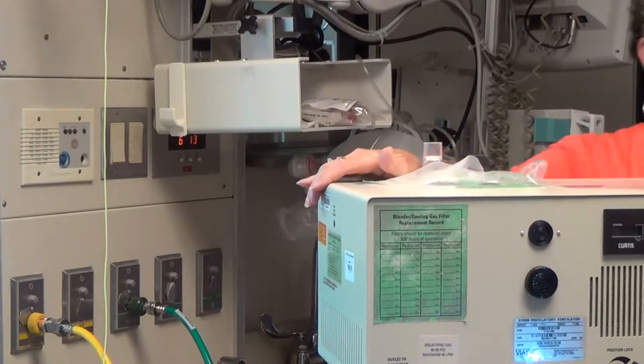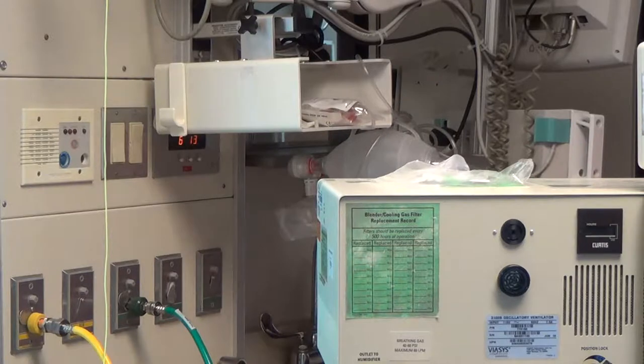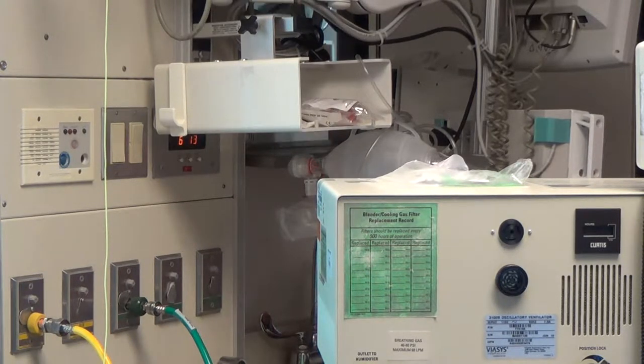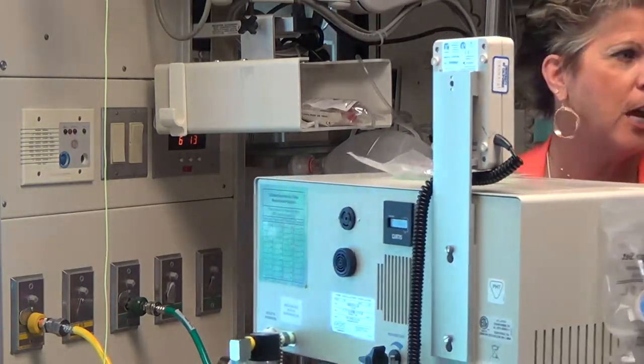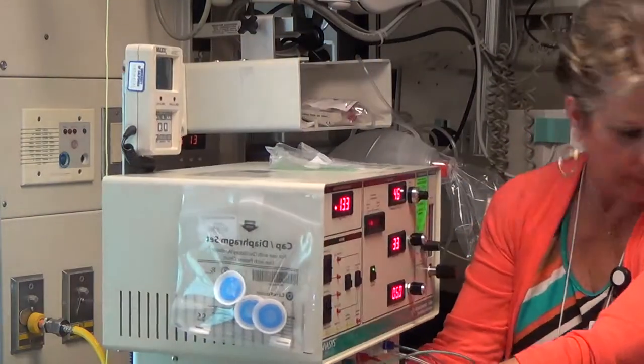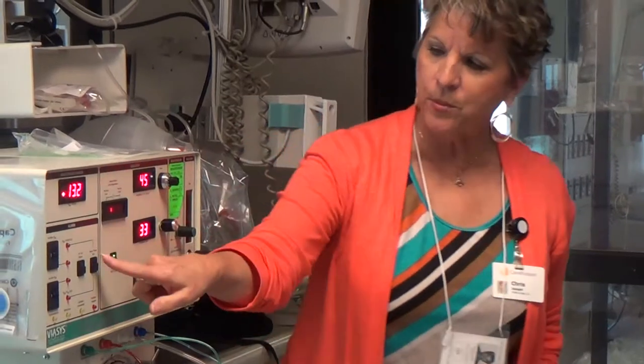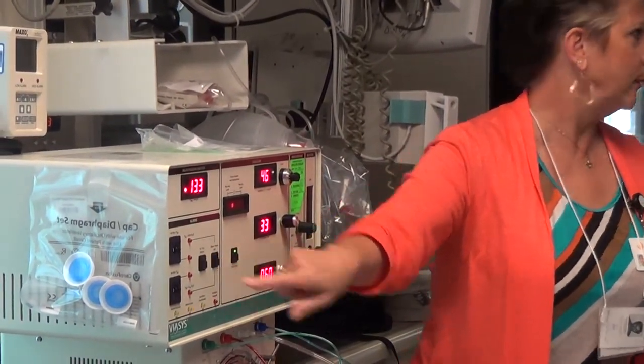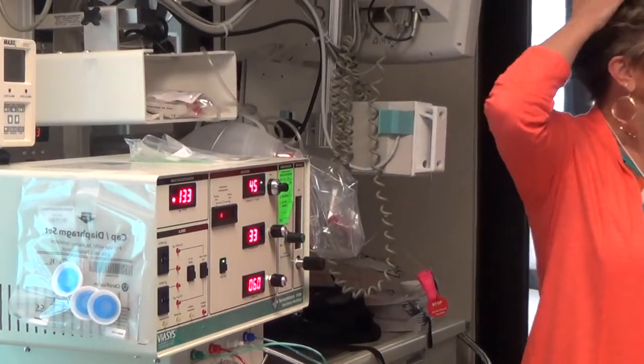Right here, you guys put your clamp there, so I guess you have to take this off too, but right behind that, there are two little screws, and you just have to unscrew the top one and it falls down, it's a little 9-volt battery, okay? You guys are testing that battery all the time. And again, you just kind of go through the motions, but watch what happens when I hit my reset. See that light go on? Your battery's good. Okay, y'all just learned something, huh?